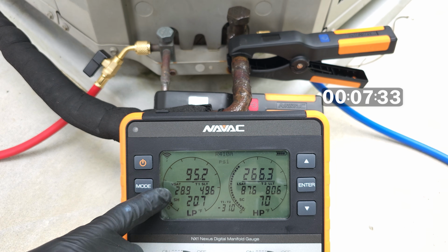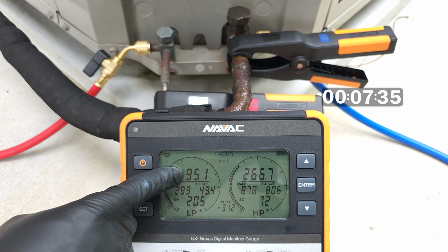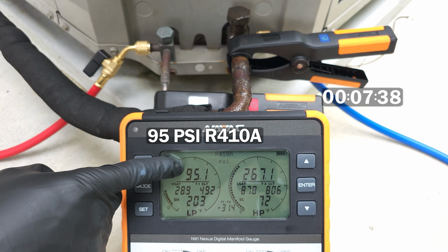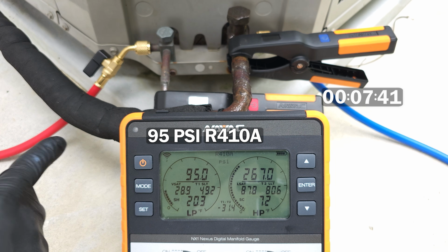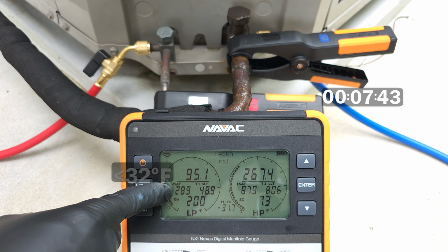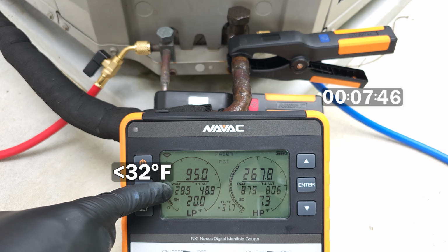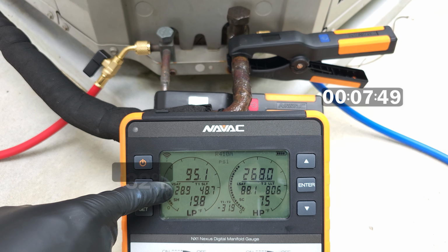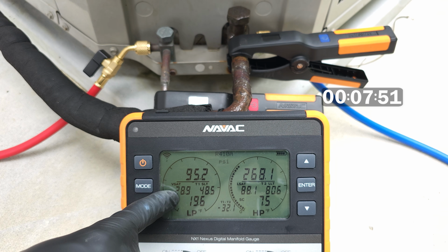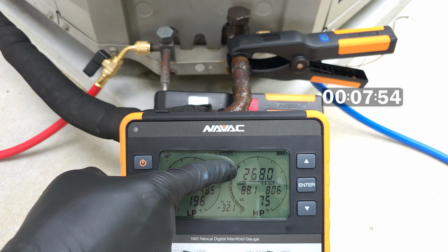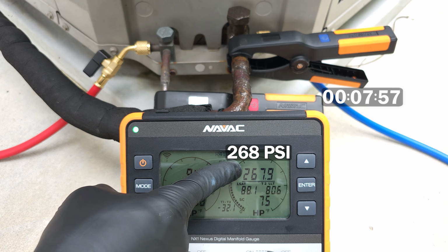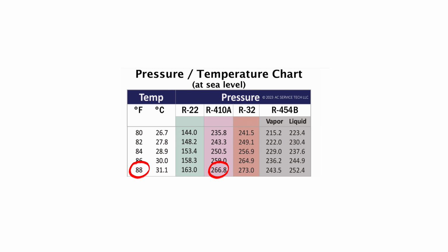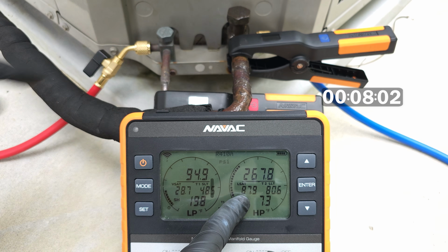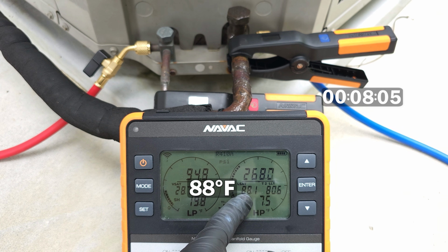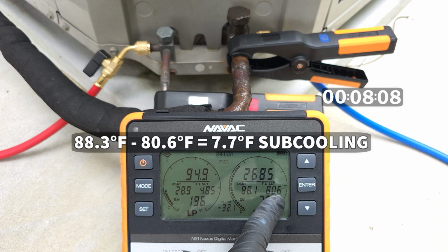So now you can see that the pressure after about 7 minutes has lowered all the way down to 95 psi for R410A at the indoor coil, and the saturated temperature is now below 32 degrees. And so any humidity in the air crossing that indoor coil is going to freeze onto that coil, and that's a problem. And so you can see over here our pressure, 268 psi. We convert that to the saturated temperature of R410A in the middle of this outdoor coil, and we're left with 87.9 or 88 degrees. So you've got 88 minus 80.6, and you have 7.7 degrees of subcooling.